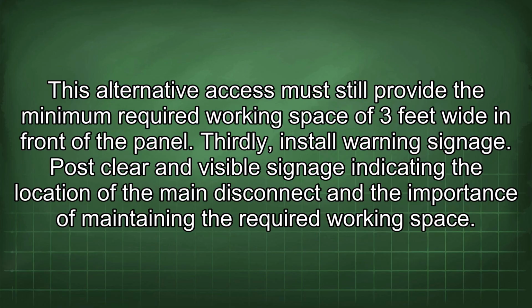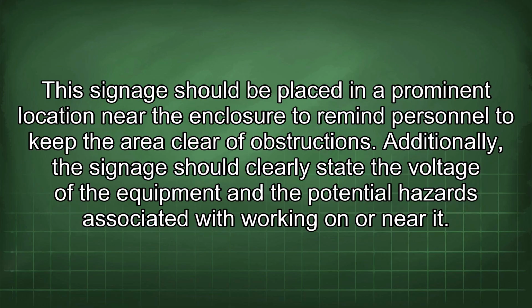Thirdly, install warning signage. Post clear and visible signage indicating the location of the main disconnect and the importance of maintaining the required working space. This signage should be placed in a prominent location near the enclosure to remind personnel to keep the area clear of obstructions.